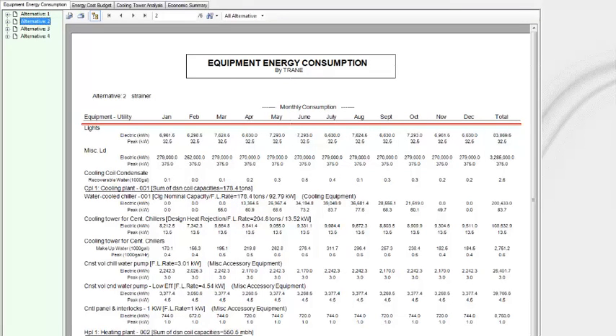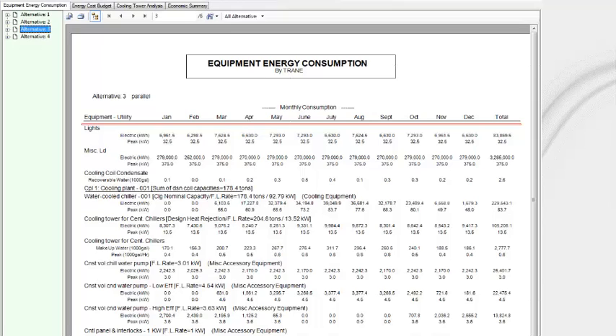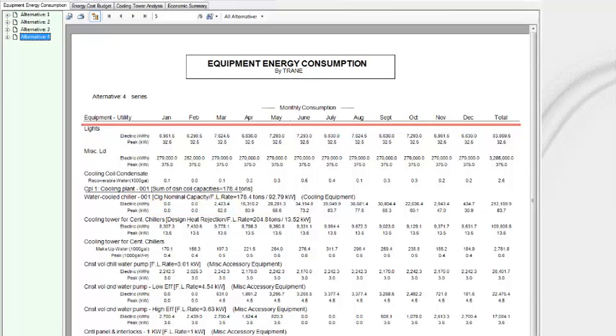When I move to the strainer cycle, it's easy to see the chiller consumption was reduced almost in half to 200,000 kWh, but the tower increased by almost 20%. And there's no chiller consumption in the winter. Alternative 3, with the parallel heat exchanger, used more cooling than the strainer and less heat rejection than the strainer, but there's also a new free cooling pump added at almost 14,000 kWh. There are some months in the winter where the cooling load wasn't met by free cooling, so the chiller had to run for some hours. The series configuration saved a bit more on the chiller at around 212,000 kWh, but the tower consumed the most energy of all four alternatives.